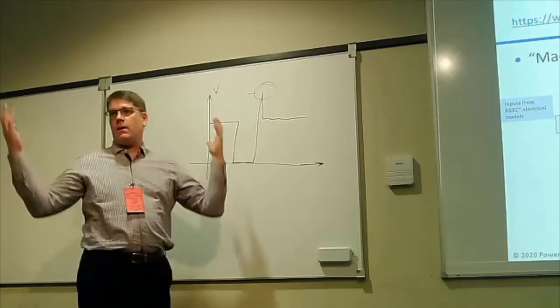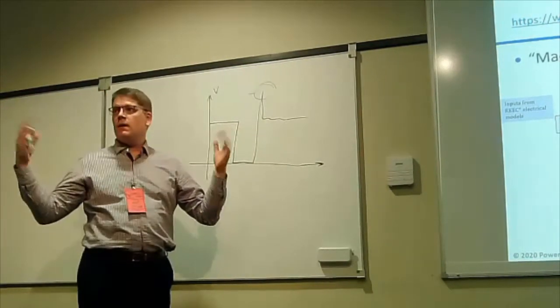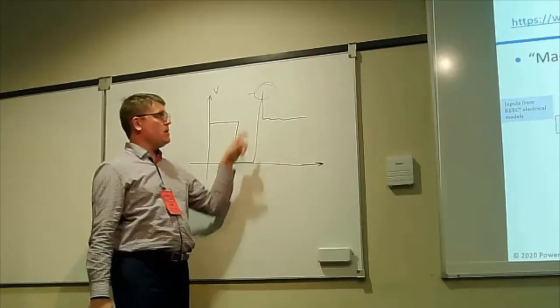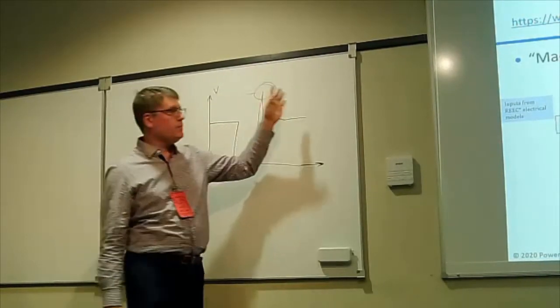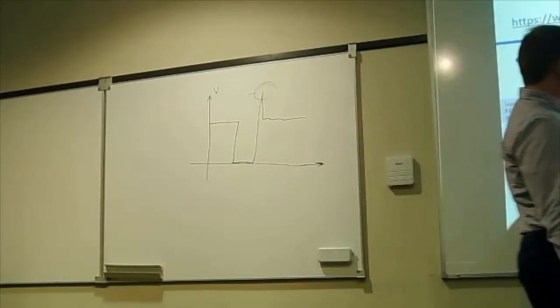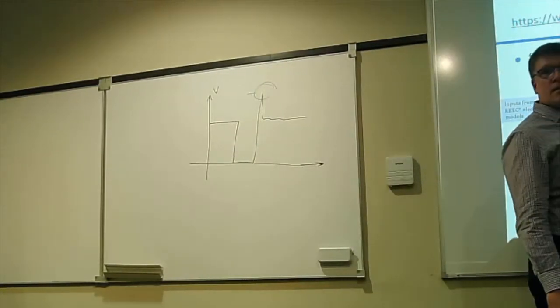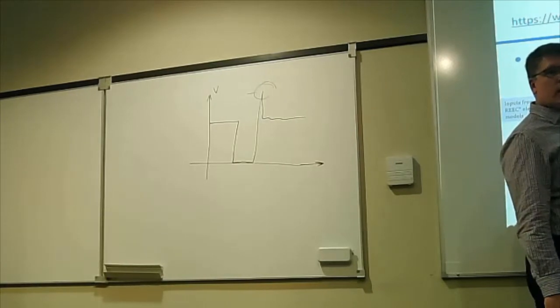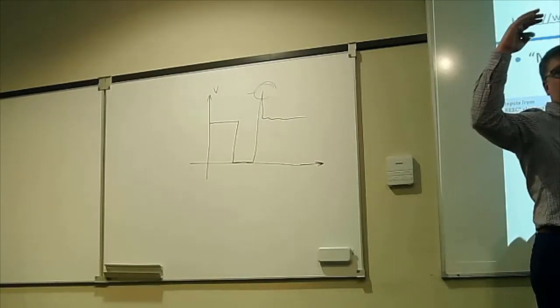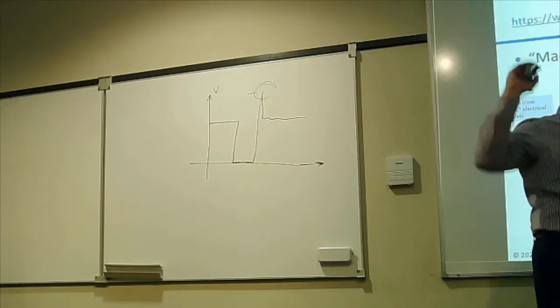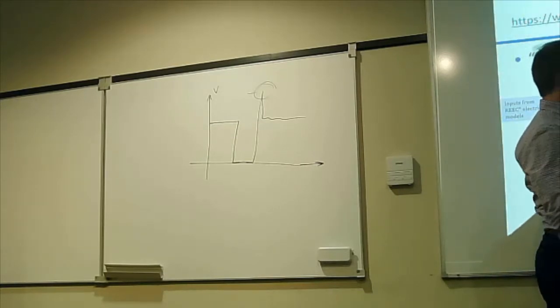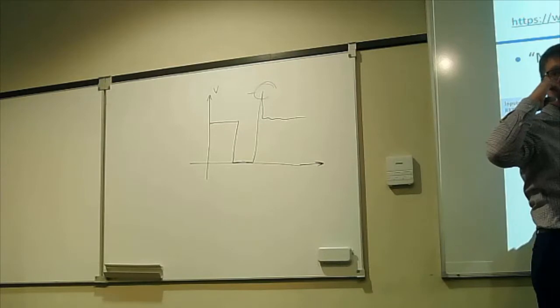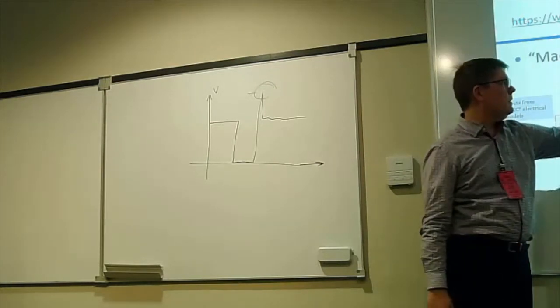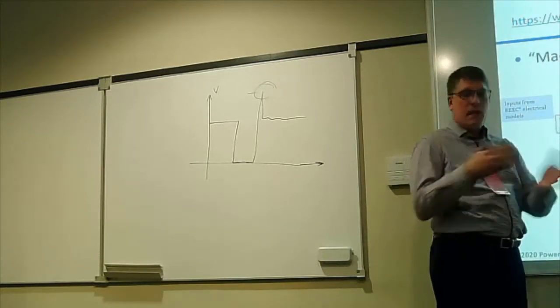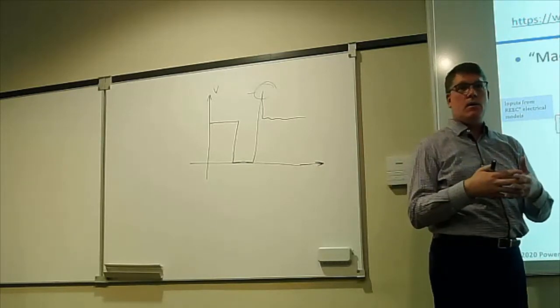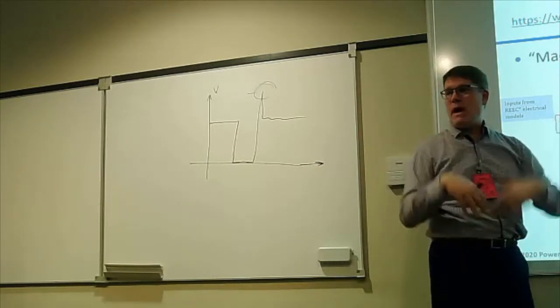Then suddenly the fault recovers, or clears, and the voltage goes from something close to 0 up to say 0.7 or 0.8. And now this signal here is still coming in as maximum current, maximum reactive current, but now the voltage is recovered. And so it's going to push the voltage way high because it's asking for maximum current when the voltage has recovered. And the problem with this model is we're not modeling every 10 microseconds in the power electronics that we go, oh, voltage recovered, I should back off now.